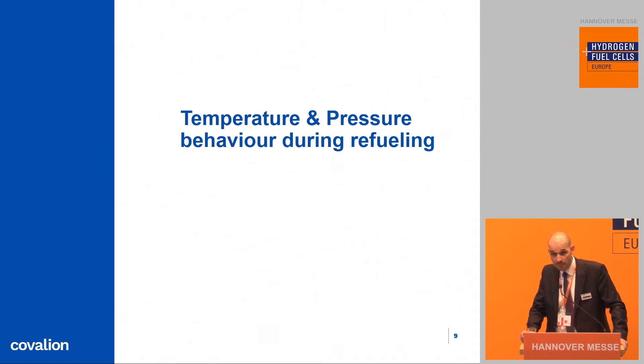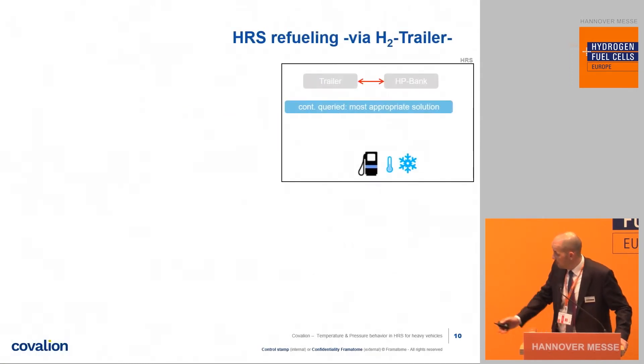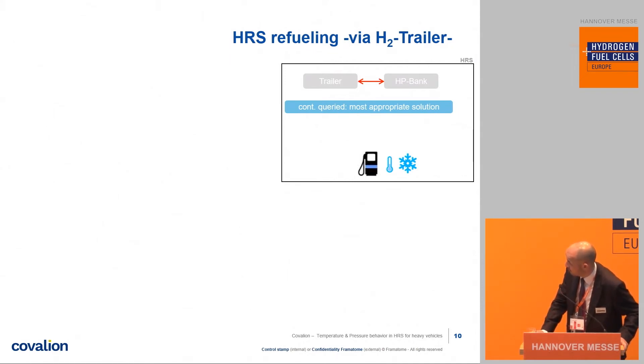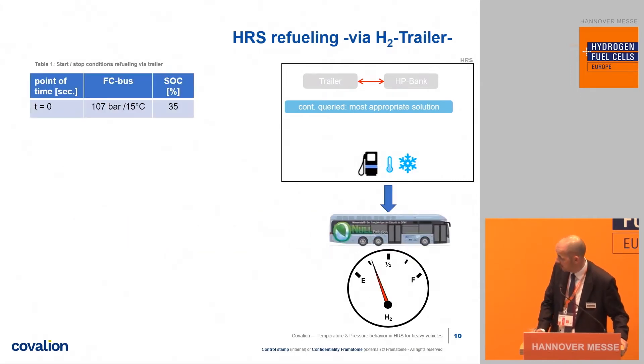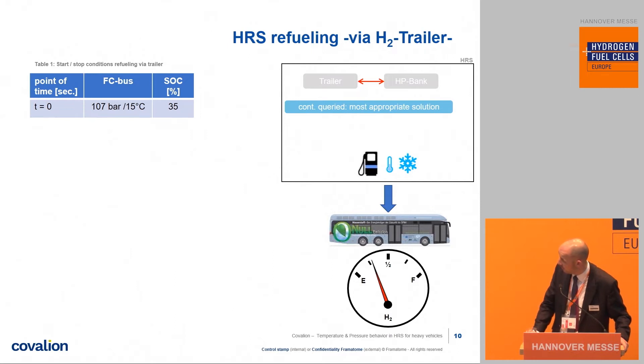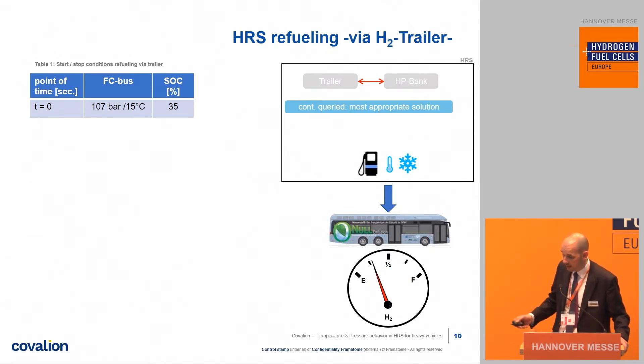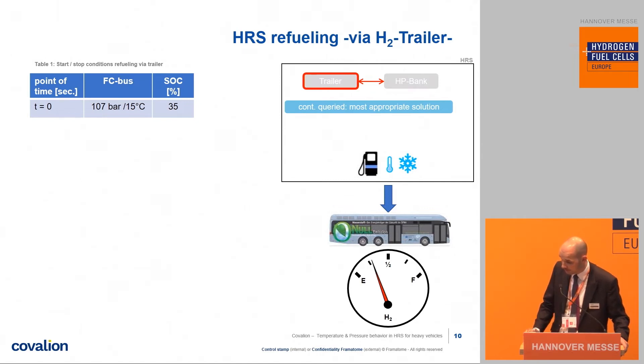Now let's look at the temperature and pressure behavior during the refueling. Here you can see a representation of our hydrogen refueling station. When a bus arrives, it is connected to the dispenser unit via a nozzle, and we determine the SOC level — the state of charge — as well as the temperature and the pressure inside the bus. In this model, it's about 35%, which means 107 bar at 15 degrees, and the target is to reach 95% SOC. The software continuously checks which is the most efficient way to refuel the bus. It determines that hydrogen from the trailer is the most efficient way, switches all the valves to the trailer, and we start the refueling.